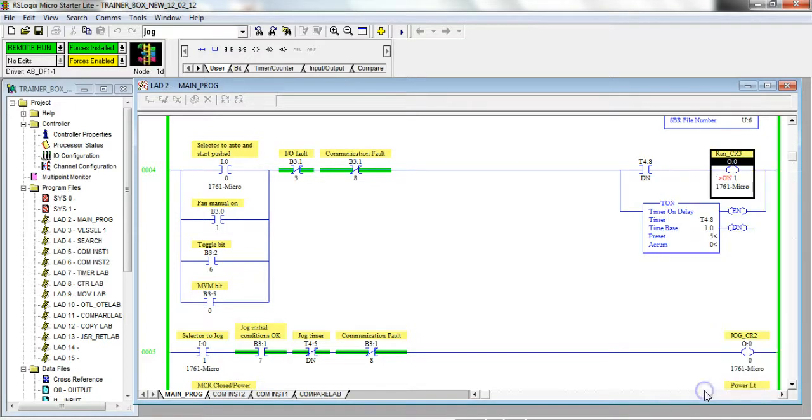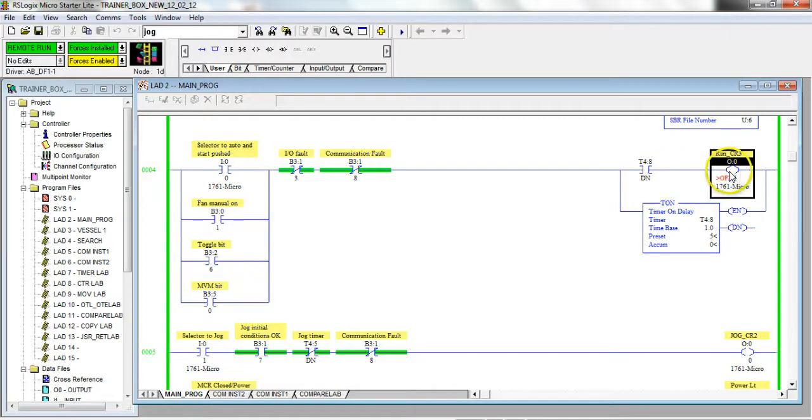Same thing down here, I can enforce it now. By the way, if you look at this there's 'force off' and 'remove force'. Make sure you choose 'remove force,' because if I choose 'force off' now, it'll never come on.